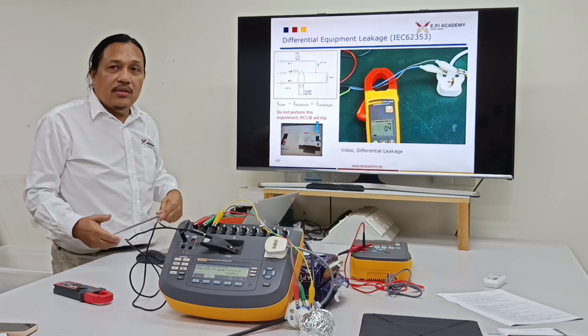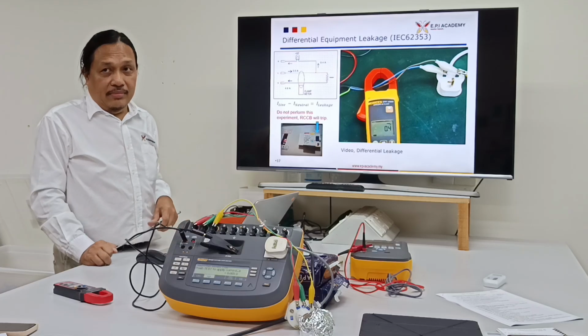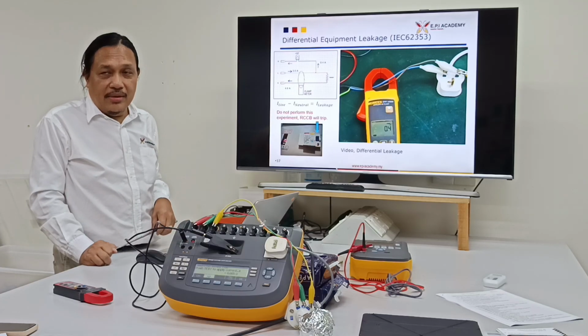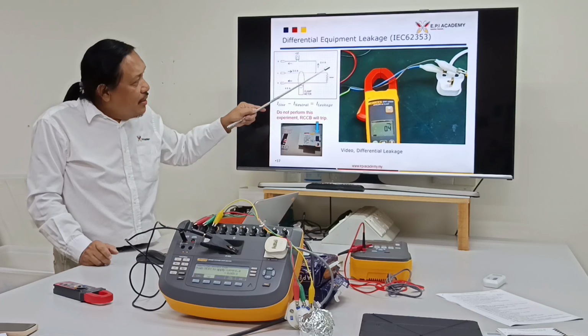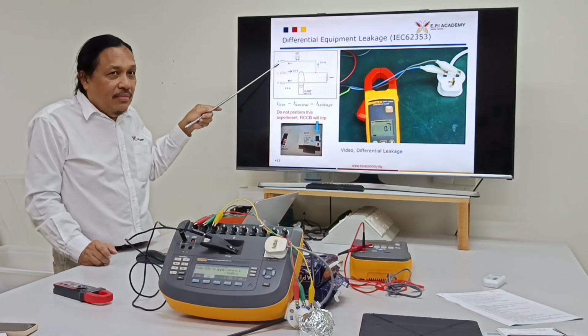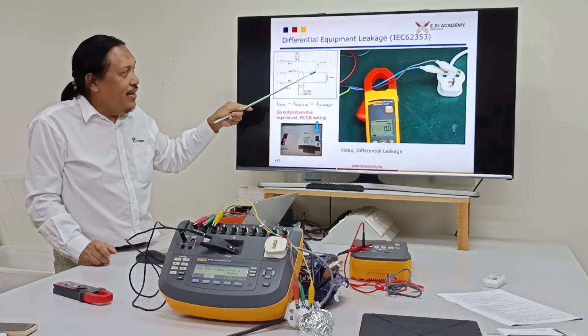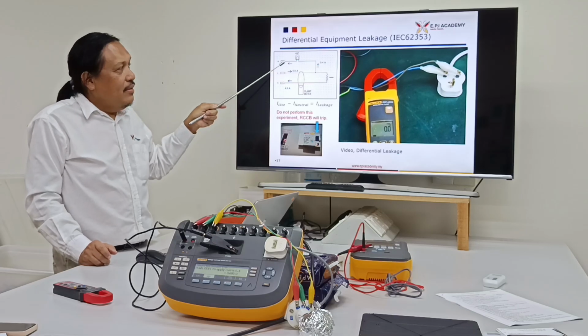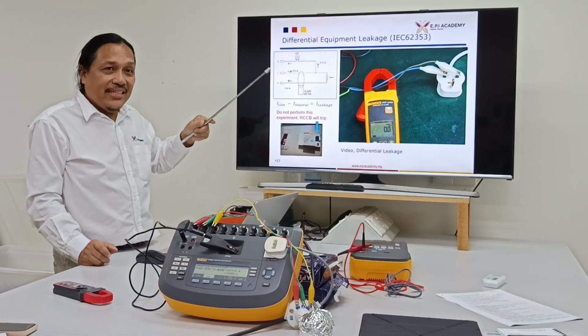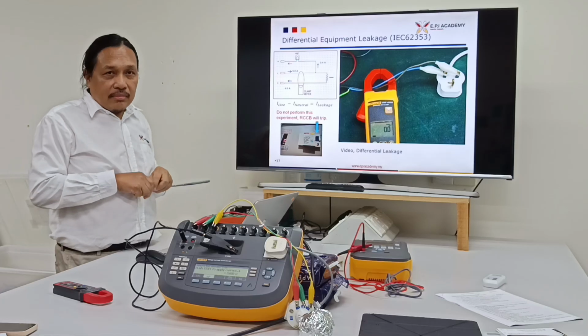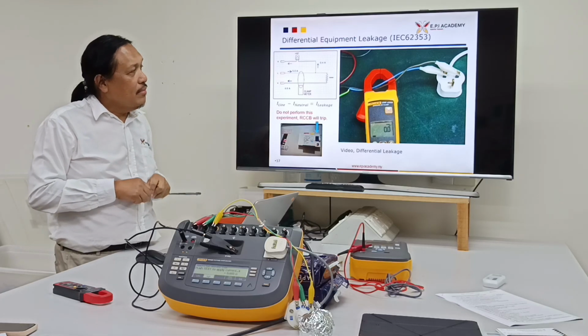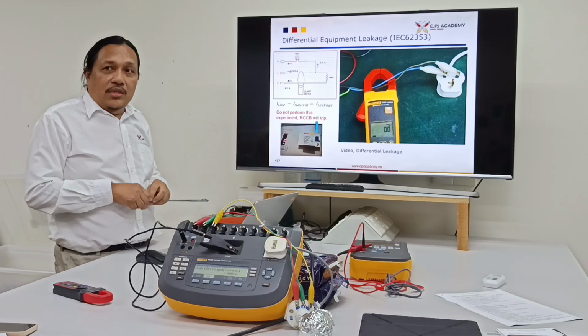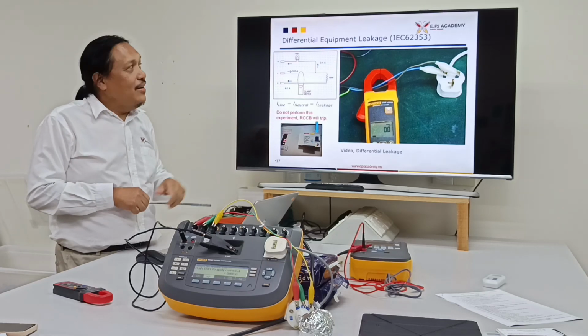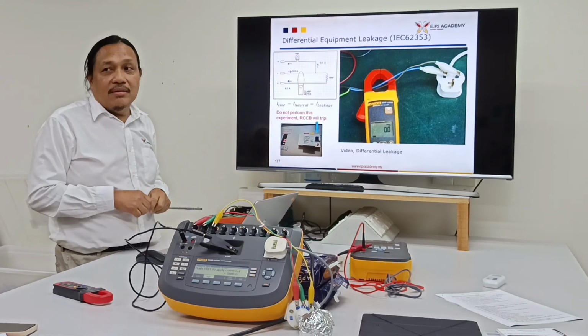That's the leakage current through the bulb. That means the leakage current, yes, the leakage current that flows through the bulb. I intentionally created the leakage current, right? It goes to ground. It's a leakage current. Check. 0.4. So, understood now how the differential method works.